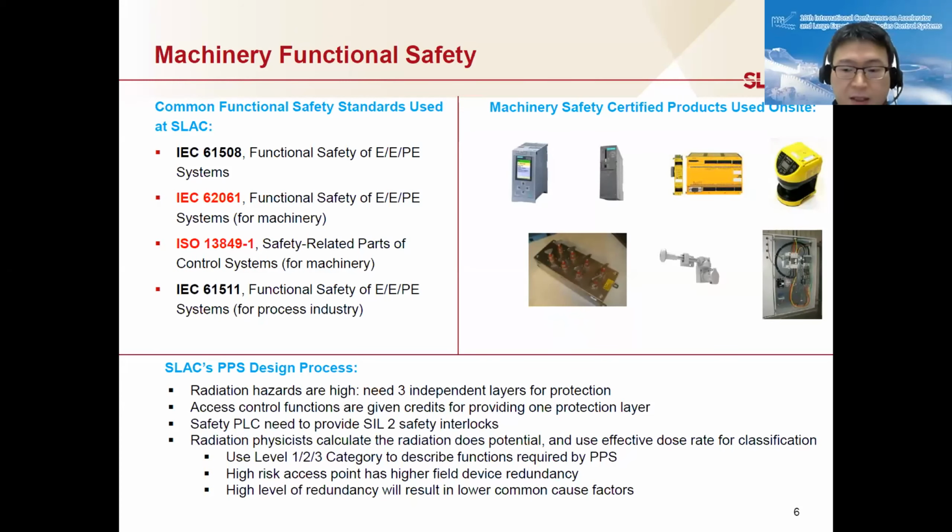SLAC's PPS design is still not fully functional safety compliant because, again, accelerator application is very special. We share something in common with the industry, but we also have lots of unique aspects. Physics drives the PPS requirement. They are not using the risk assessment that functional safety people typically use. For example, our radiation physicists use level 1, 2, 3 to try to categorize what kind of PPS device is needed in the field.